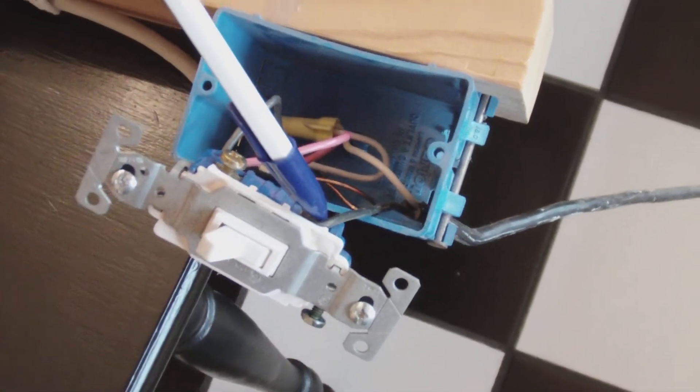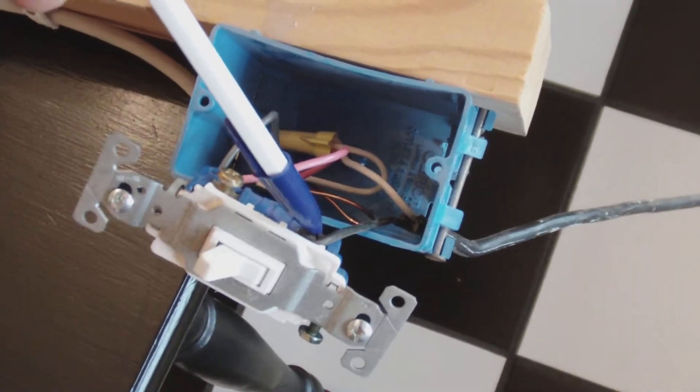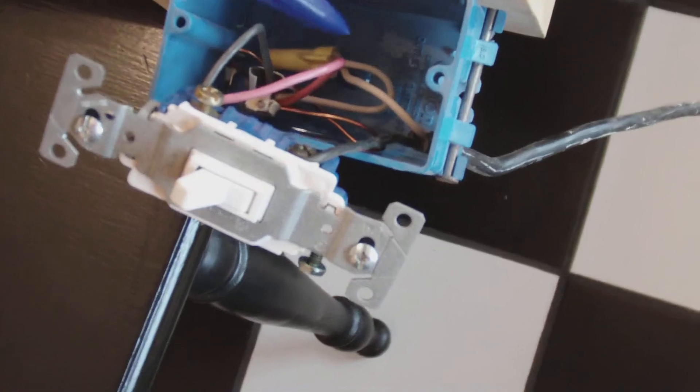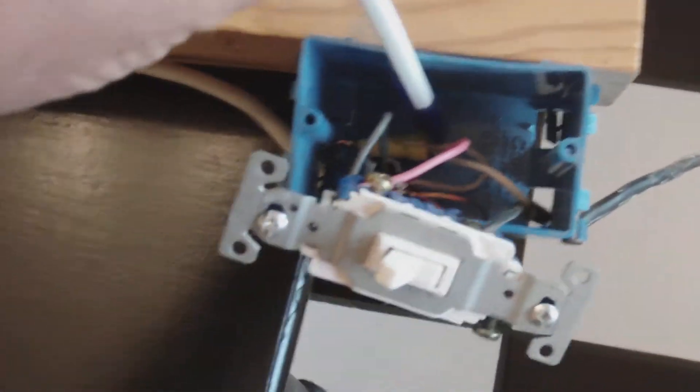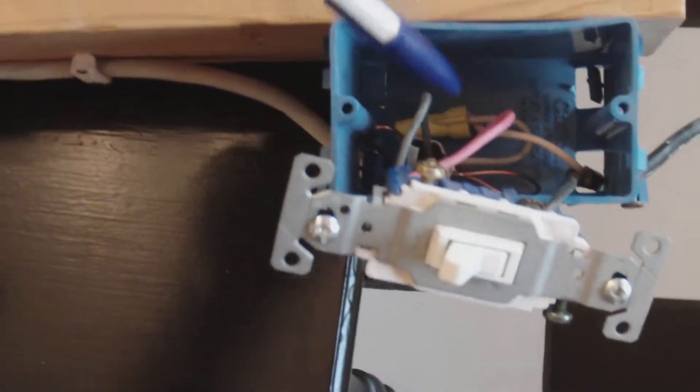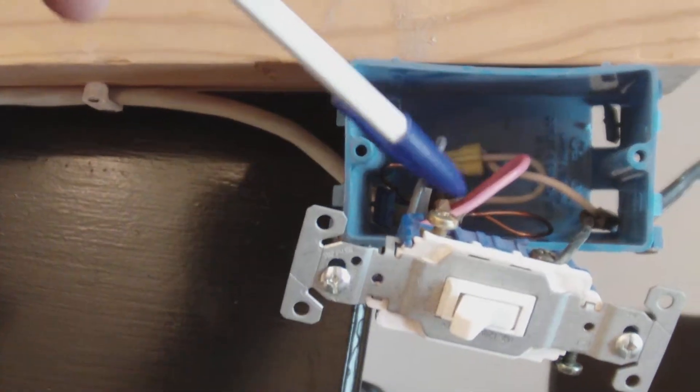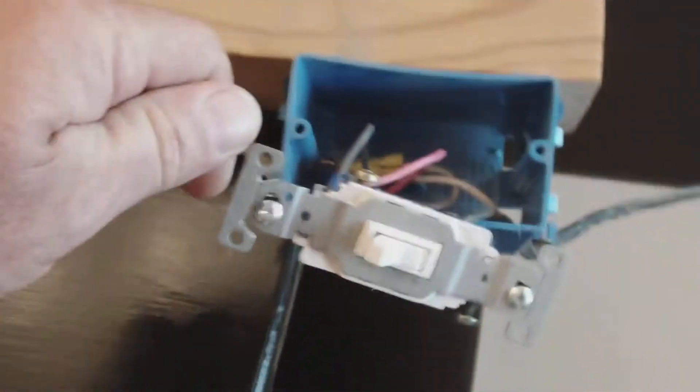Simply take the black power wire and connect it to the black screw on the three-way switch. That will leave you with the white wire connected here. Then your traveler wires, which are black and red, you can connect them to either side of this switch. It makes no difference, either side.